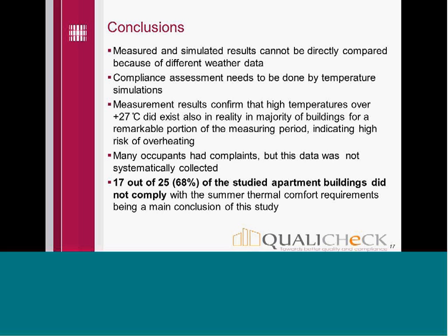That's the reason the compliance assessment needs to be done based on the temperature simulations. But these measurement results confirmed that high temperatures over 27 degrees did exist also in reality, in the majority of these buildings for a remarkable portion of the measured period, indicating a high risk of overheating.